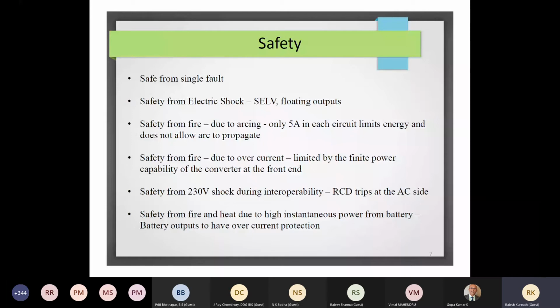In higher voltage DC systems, this is a huge problem, unlike AC systems, wherein the AC goes through a zero, which automatically quenches the arc. But in a DC system, if you're looking at a 330 volt or 450 volt AC system, a 450 volt DC system, the arc will travel. Therefore, all these standards or areas which use high voltage DC need special ways in which arcing has to be identified and suppressed. Whereas in voltages up to 60 volts, it's not a problem. And there have been a lot of studies done at 48 volts as well, that 5 amperes at 48 volts does not lead to a case where an arc is going to propagate.